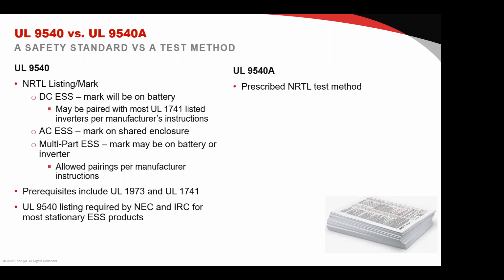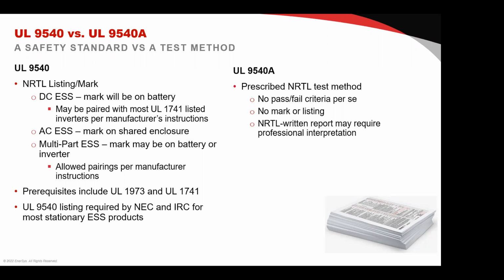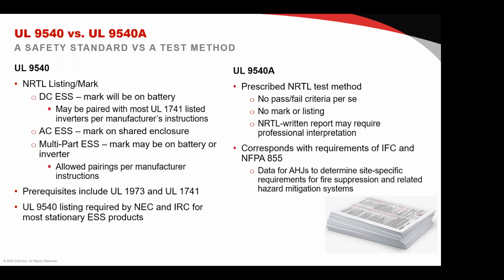So UL 9540A is a test method. There's no pass-fail criteria. There's no mark or listing. Okay, so it's not a listing with a mark on it that says UL 9540A. It's a written report that will probably require some professional interpretation by the local planning board or system designer. It corresponds with what's required by the IFC and NFPA, and the data is going to be used by the local authority having jurisdiction to determine any site-specific requirements for fire suppression and any other hazard mitigation systems, like if there's explosive gas that can be emitted when there's thermal runaway. So it's not saying that there will be fire suppression or other hazard mitigation systems required, but they will look at the data of the test.